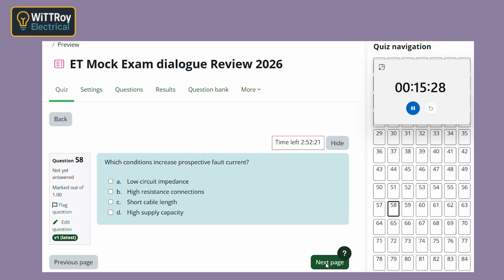Question 58. Which conditions increase prospective fault current? Low circuit impedance? Yes, the lower the impedance, the higher the fault current. That's a very important relationship. So shorter cable length also matters because shorter cable means less resistance. Exactly. Shorter length generally means lower impedance, so the fault current can be higher.